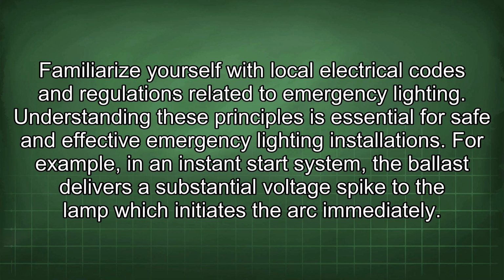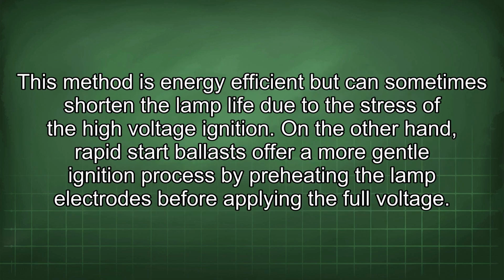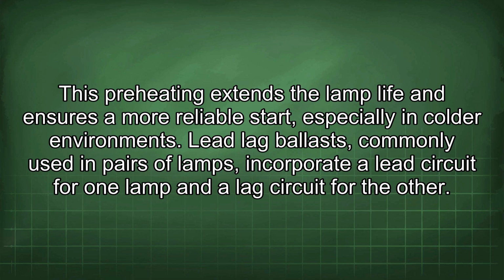For example, in an instant start system, the ballast delivers a substantial voltage spike to the lamp which initiates the arc immediately. This method is energy efficient but can sometimes shorten the lamp life due to the stress of the high voltage ignition. On the other hand, rapid start ballasts offer a more gentle ignition process by preheating the lamp electrodes before applying the full voltage. This preheating extends the lamp life and ensures a more reliable start, especially in colder environments.